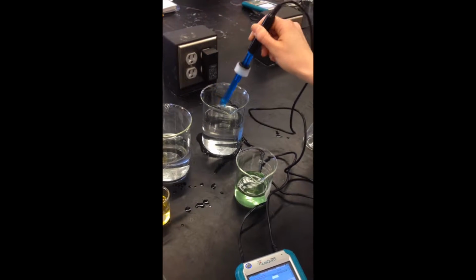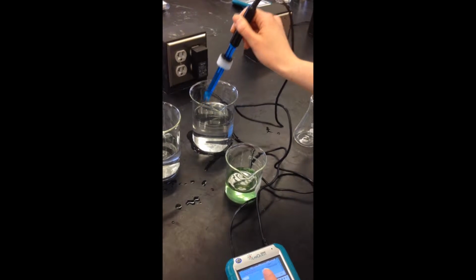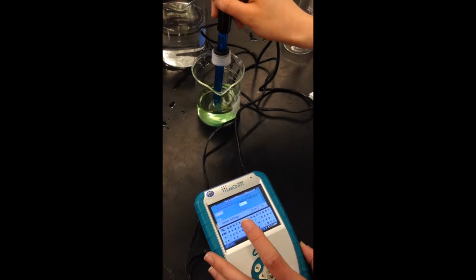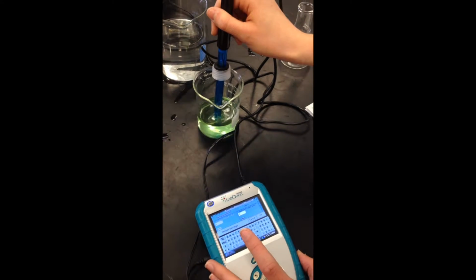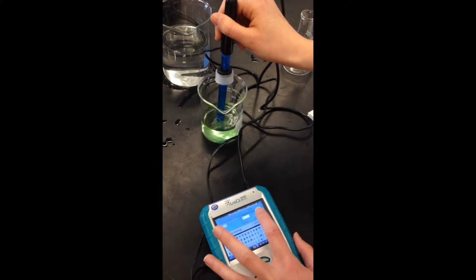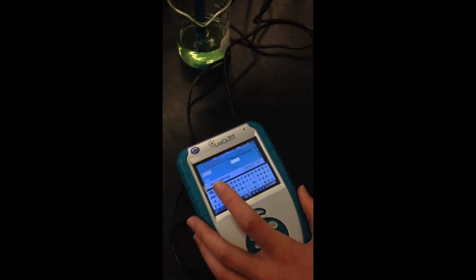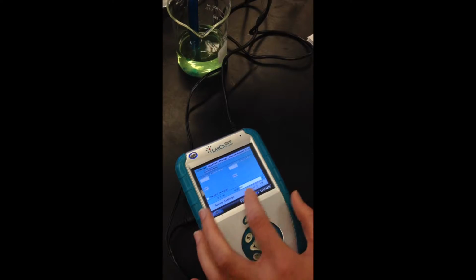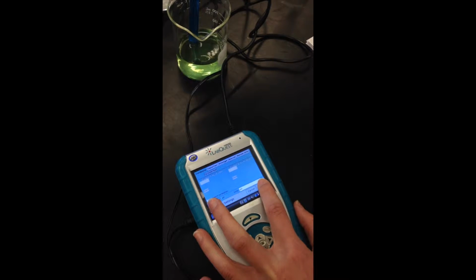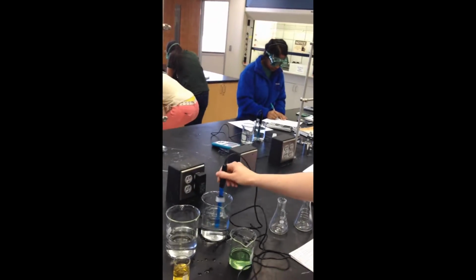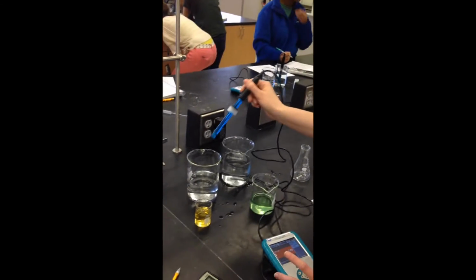We're going to go ahead and put 7 down here. We're going to stick it in the pH 7 buffer solution and wait till the voltage stabilizes again. Okay, and it looks like it stabilized at 1.7, and we're going to hit keep. And then hit OK. And then we're going to take our probe and rinse it in the water one more time. And then put it in the storage.